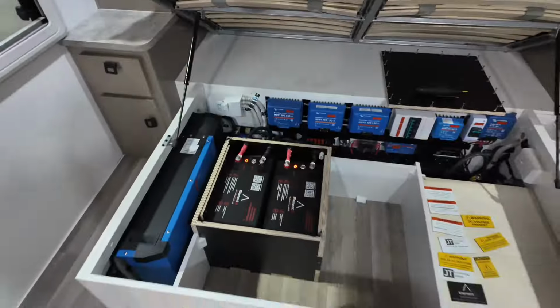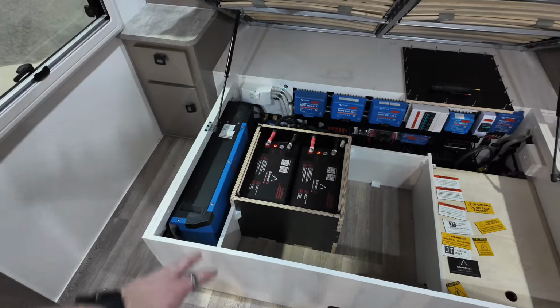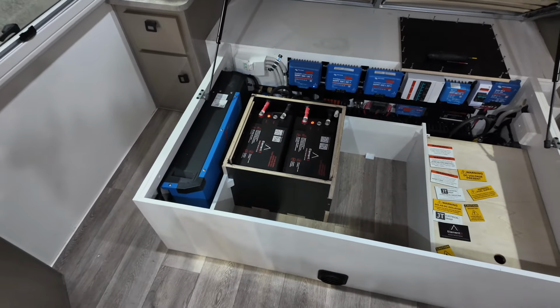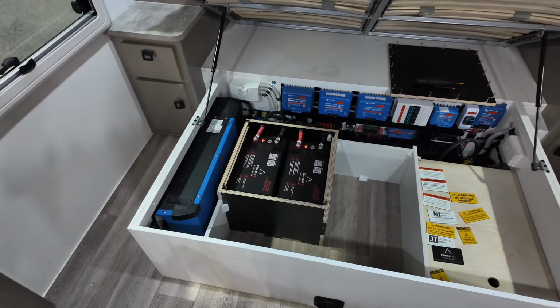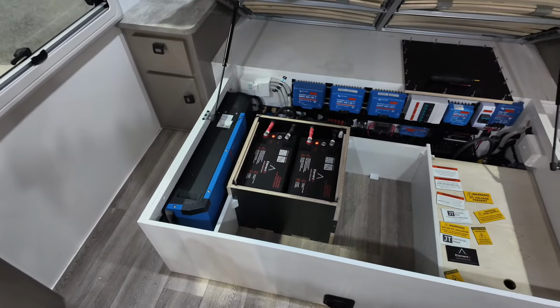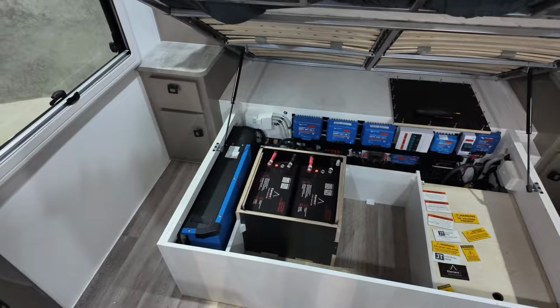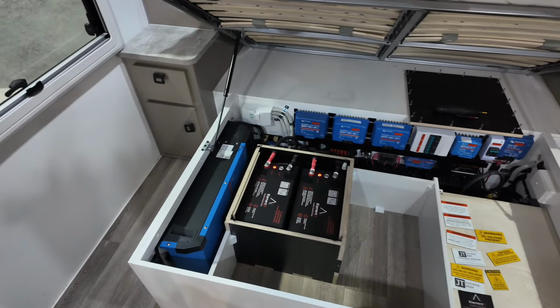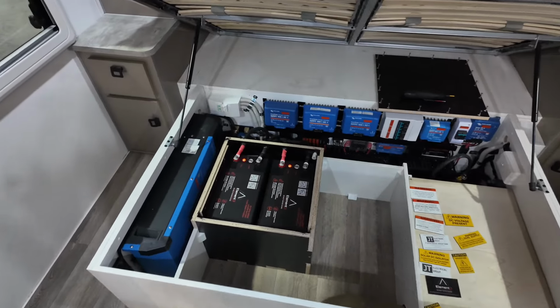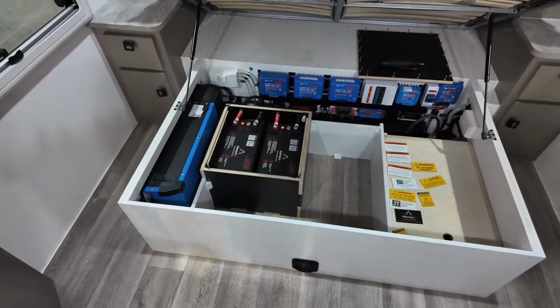So it can be done. If you only had the one battery, 100% I would not advise it. If you have the two to share the load of the heat, that is okay. You've got two circuit breakers, you've got two batteries. If you only have one of each, absolutely not. I'd say do a 24 volt system, and that's the only time I would say to do that.